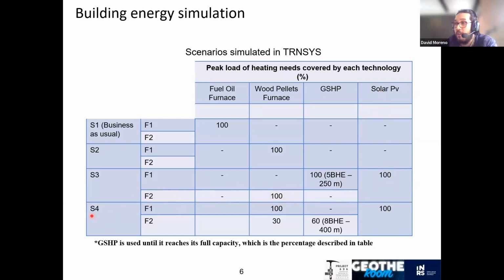For scenario 4, the heating needs of the first floor are covered by the wood pellet furnace, and the heating needs of the second floor are covered 30% by the wood pellet furnace and 60% by the ground source heat pump. In this case, the configuration is 8 borehole heat exchangers of 50 meters each, for a total of 400 meters. Also here, the electricity needed to run the heat pump is covered by solar PV.